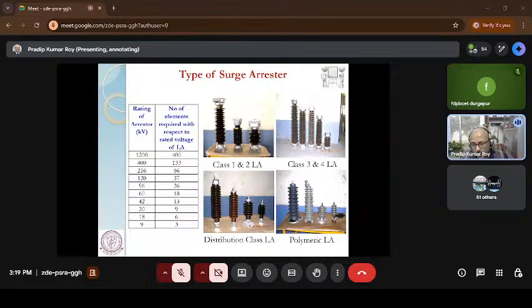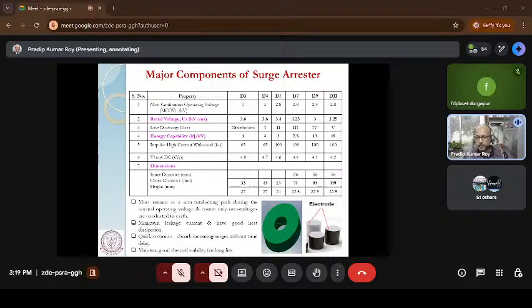So the demand has come from industry: how can we reduce the height of the surge arrestor by increasing the rating of the block so that the number of blocks can be reduced? For example, I need the same 1200 kV arrestor. Is it possible to make it with only 200 blocks? Okay, but the rating of the surge arrestor will remain at 1200. So how do you define the materials part here?